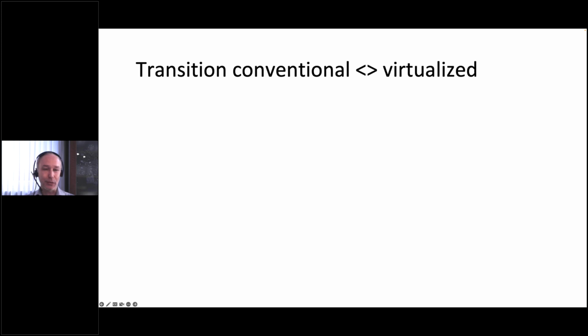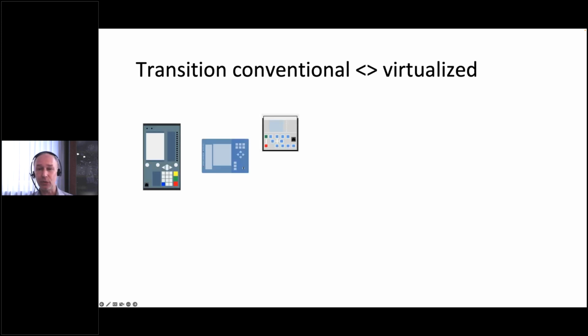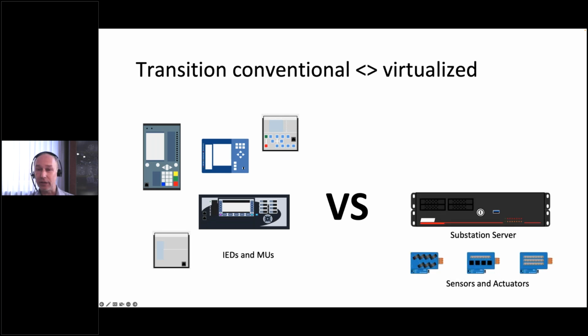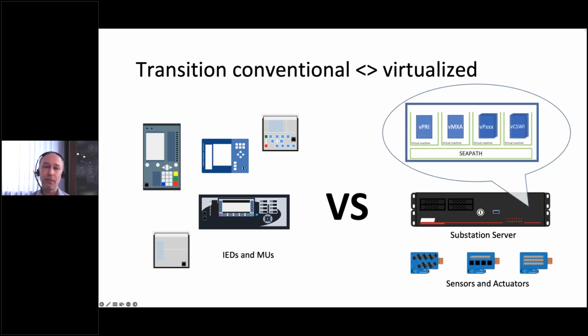Nowadays it's very common to use multifunctional IEDs. Many of these IEDs integrate process functionality like TCTR, TVTR, and substation functions like measurements, control, switchgear, and protection functions, all in a single box. Some of this functionality is not needed and therefore unused, but you pay for it nevertheless. Also, having many merging units and IEDs installed in a substation results in additional copper wiring and more complex network infrastructures.